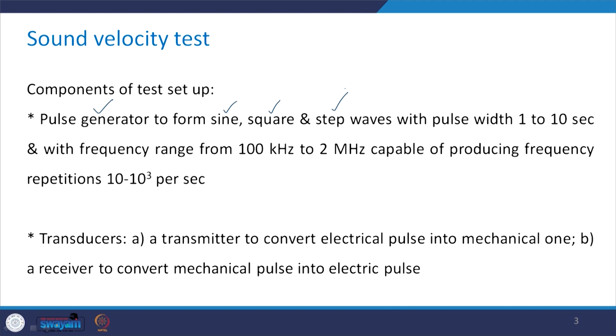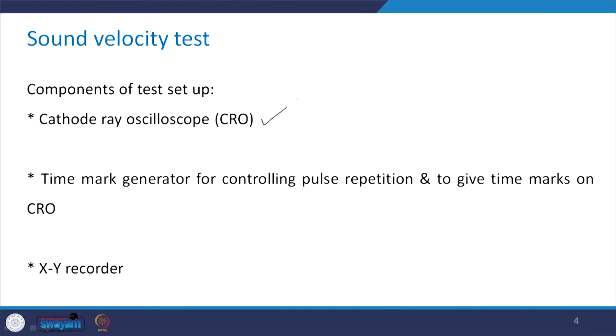Then there are transducers. The first one is a transmitter which converts the electric pulse to the mechanical pulse, and the second one is a receiver which converts the mechanical pulse into the electrical pulse. There are other components like a cathode ray oscilloscope, a time mark generator for controlling the pulse repetition and giving time marks on the oscilloscope, and an XY recorder.